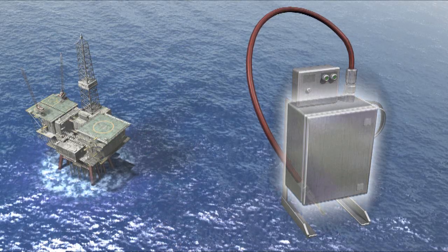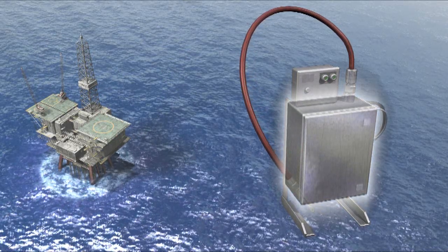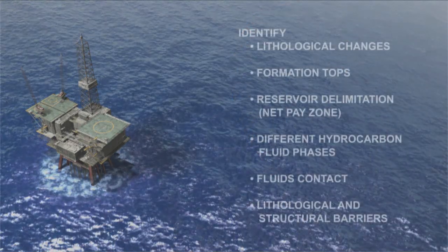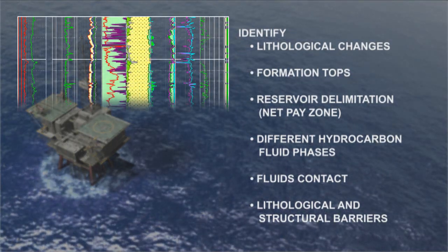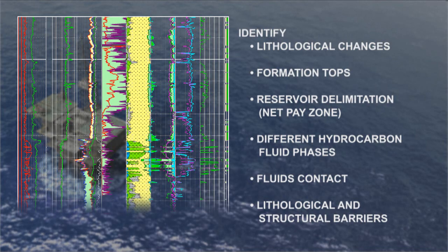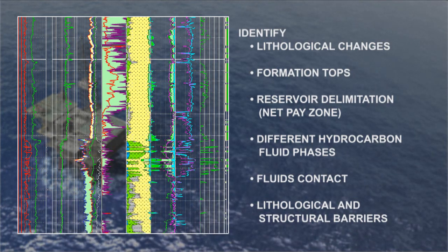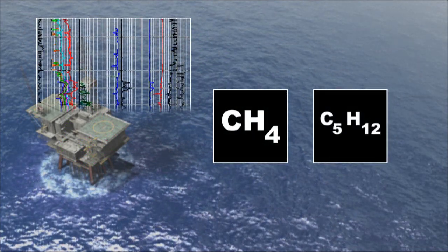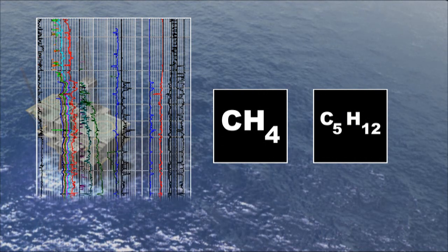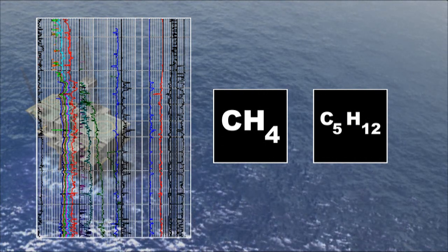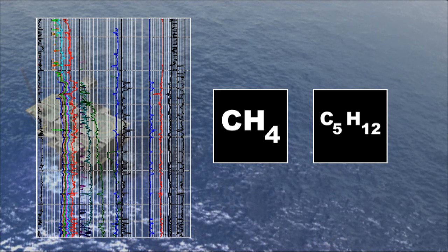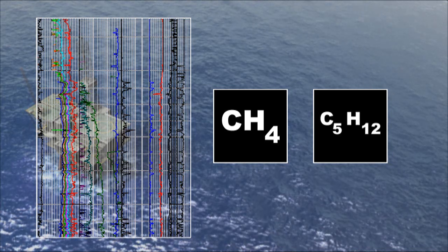Inside the enclosure, the system's high-speed gas chromatograph enables fast and precise analysis of the samples. Hydrocarbon gases from methane to octane can be analyzed in less than 1 minute. So can non-hydrocarbon gases such as nitrogen and carbon dioxide. When run in express mode, methane to pentane can be measured in just 20 seconds. Compare that with other systems which can take up to 5 minutes to sample the same range. The GCTracer's speed dramatically increases the resolution of data capture and reduces the risk of missing bypass pay and weakly defined zones.